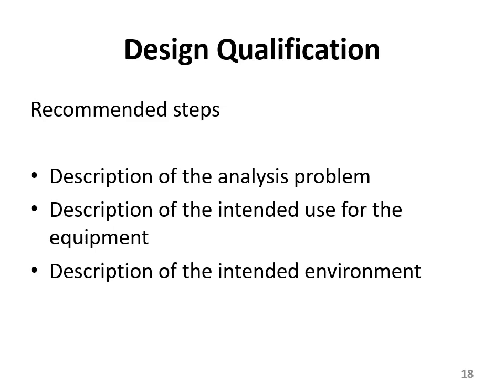And some of the important scopes of the design qualification or design validation protocol are to verify that the design will achieve the user requirement specification, whatever it is, and verification that the system will be calibrated. Whenever you use it, calibrate it. Apart from that, one or two more important things are: just write down. If you are getting some flaws, some faults, or you are facing some hardships, just write down and redesign your process and redesign the things.